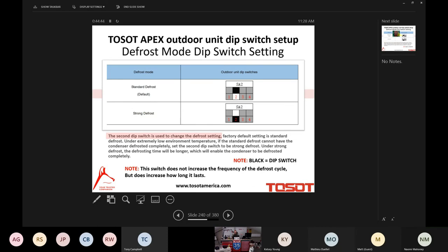Now, we're going to set the defrost mode with switch number 2. The default is the factory setting, and that's what you see here, the standard with the switch in the up position. But you can, or your installer can, switch it to the strong defrost. What that does, it doesn't increase the number of defrost cycles, doesn't do that at all. It simply takes the number of cycles and elongates them, makes this defrost cycle longer, so that if we do have an unusual amount of frost, ice on the outdoor unit, it will give it additional time in order to overcome that. In your extreme climates up there, maybe something you want to take a look at and enable.